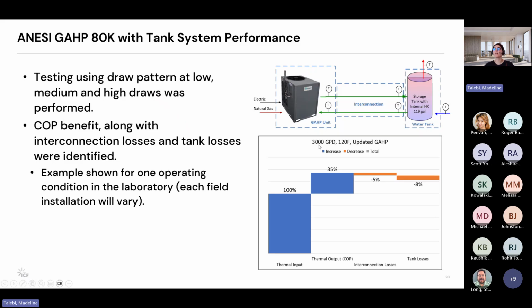So this was looking at one data point, just to exemplify this type of behavior, what we might expect. If the COP is, let's say, about 1.35 according to this graph, the interconnection losses might fluctuate. It depends on how it's configured. Of course, there are a lot of studies happening right now trying to make a blanket tool that looks at how you install these GAHPs to get the most efficient configuration. So that might fluctuate, but the tank losses are innate to the system. So if we look at what the overall COP is going to be with this indirect storage tank linked to this GHP unit, with a 1.35 minus the 8% losses, you could still expect about 1.27 COP, which, again, is to be expected based on some of the part load data and is a very positive finding in this case.